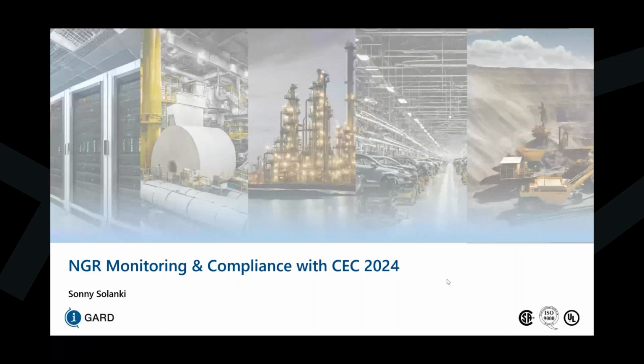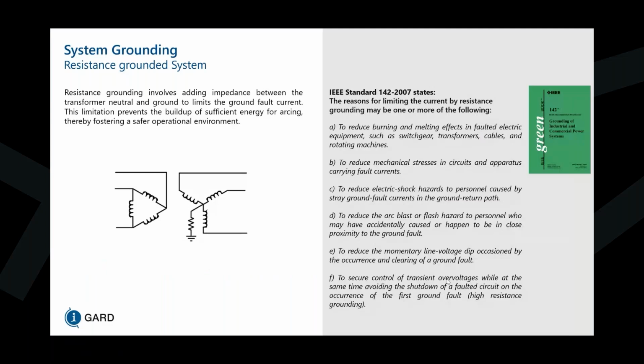So to start off, for system grounding, resistance grounding typically involves adding an impedance between the transformer neutral and ground to limit the ground fault current, and this limitation prevents the buildup of sufficient energy for arcing, thereby fostering a safer operational environment. So instead of the typical scenario where we have a solidly grounded connection from XO to ground, we instead place a neutral grounding resistor in an effort to limit any phase to ground fault by putting a resistor in series so that we can clamp the current level of that ground fault.